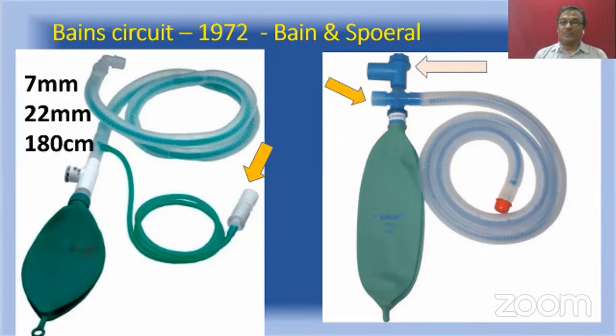Look at that valve. The valve has a scavenging attachment. So scavenging of expired gas is possible with this modified version, while that is not possible with the older version. So the advantage of this particular one is that scavenging is made easier.